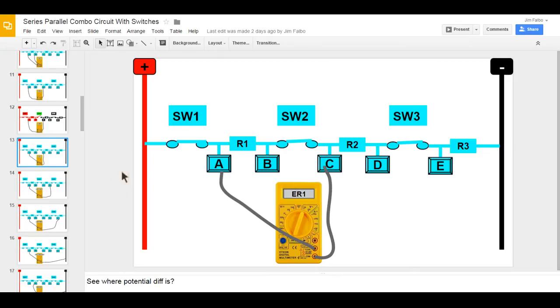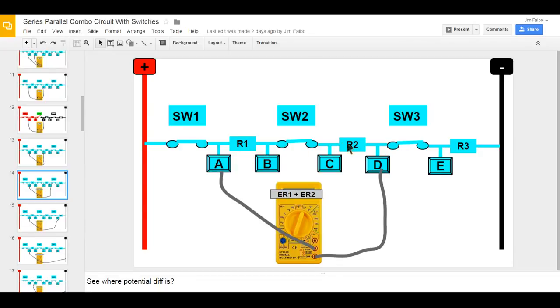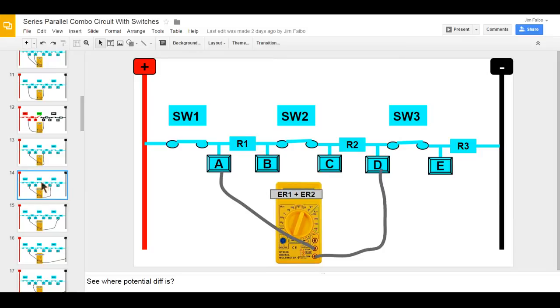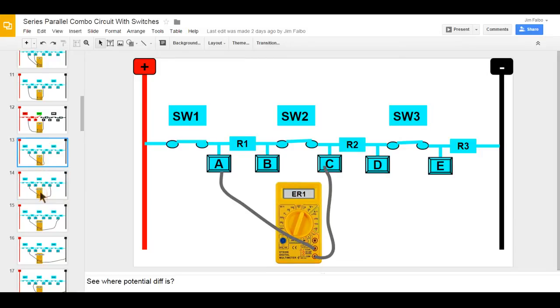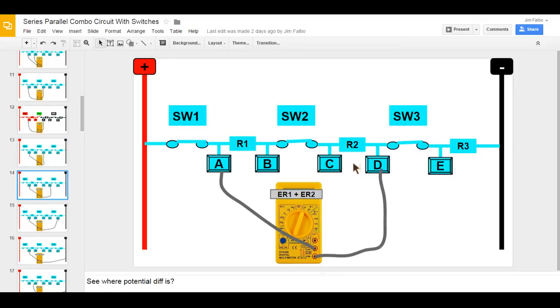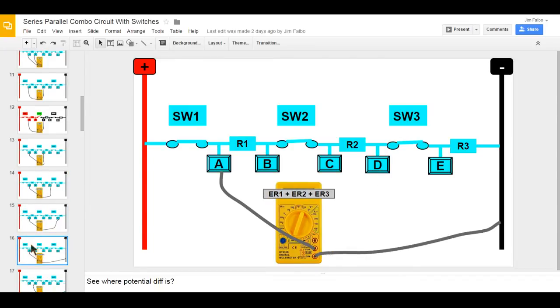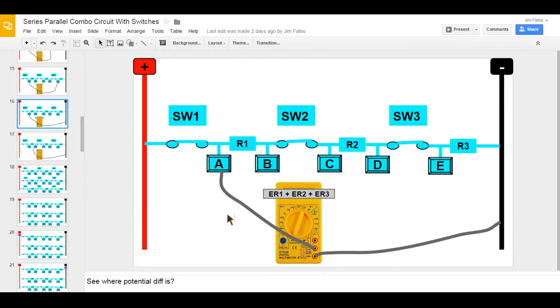Closing switch two again, I'm still only seeing the voltage drop across the first load. Moving the lead from C to D, I see the voltage drop across two loads. I don't need to do any math — I just need to remember the series circuit rule: the sum of voltage drops. When I move that meter lead over I should see an increase in voltage drops. If I see no change between two points, I know there's something wrong with that load. Here I'm still seeing the same reading, and now I see full supply voltage because this is like reading across the main bus.